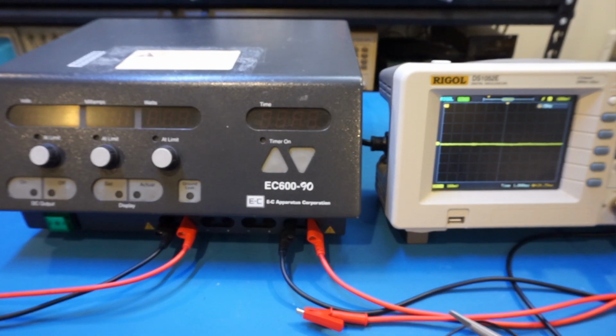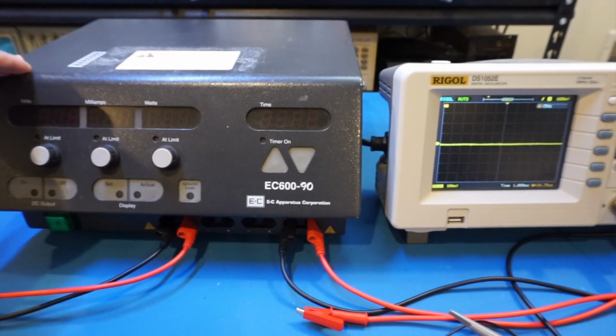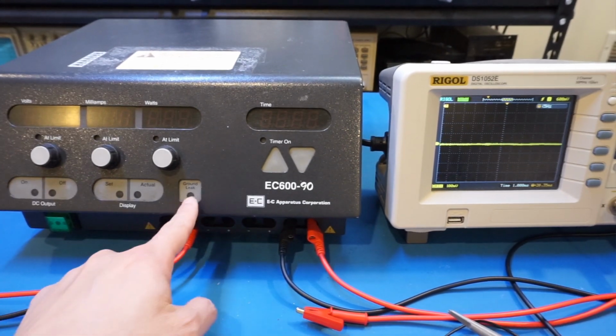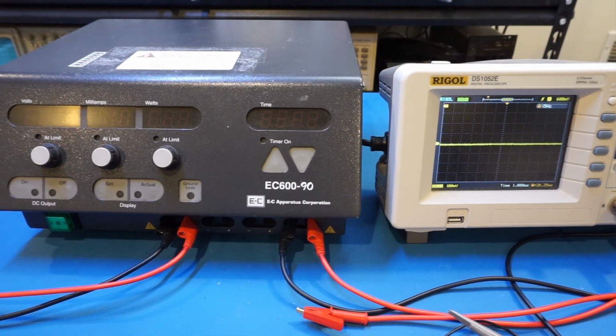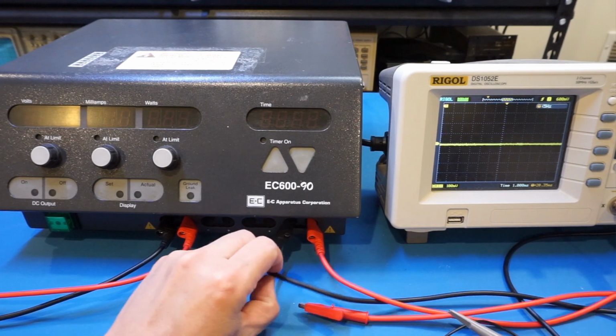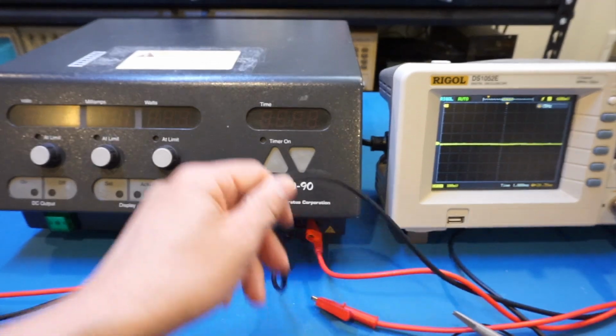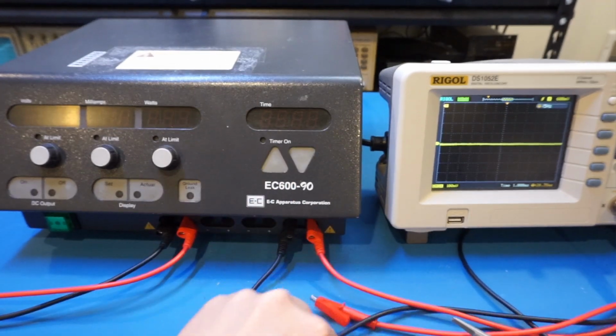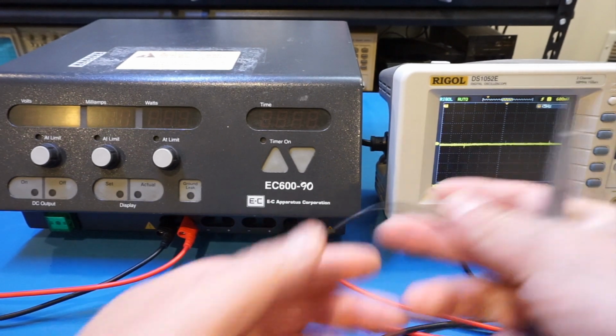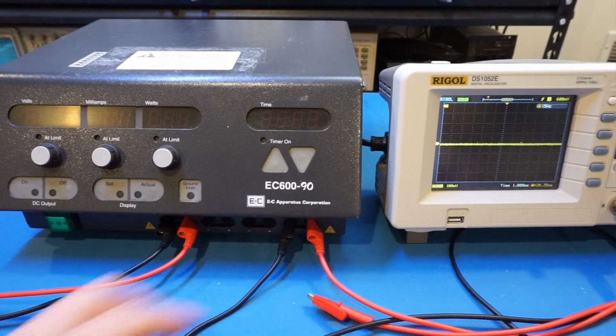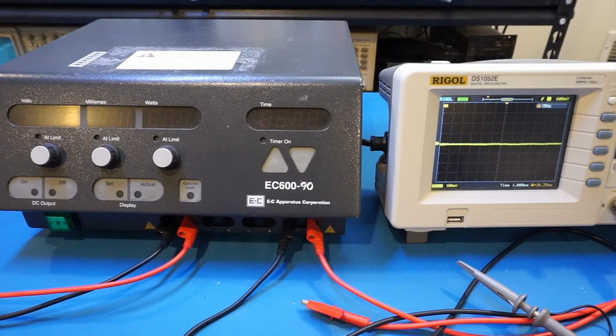So what I didn't tell you is that this power supply, the EC600-90, also has a ground leak detection feature. If any current leaks into the earth, that's when a ground fault occurs, and this power supply would cut off. So what I'm suspecting is that the negative terminal here is actually not grounded—it's isolated. So when you connect the oscilloscope's earth terminal to that negative, it causes this ground leak condition to happen.